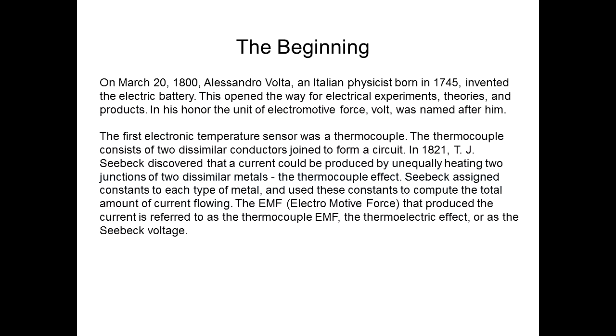The first two temperature sensors were thermocouples and RTDs. The first one was a thermocouple consisting of two dissimilar metals joined together to form a circuit. In 1821, T.J. Seebeck discovered that a current could be produced by unequally heating two junctions, what's called the hot junction and the cold junction of two dissimilar metals, the thermocouple effect.